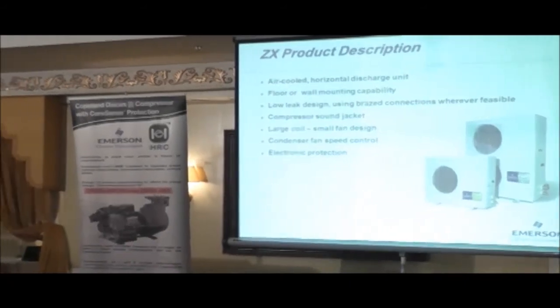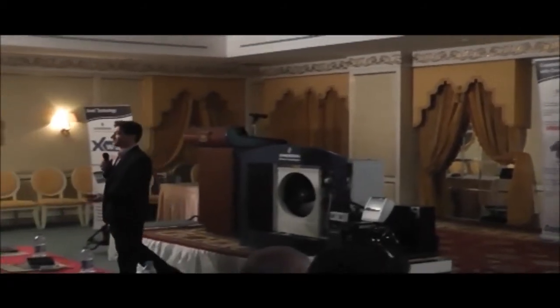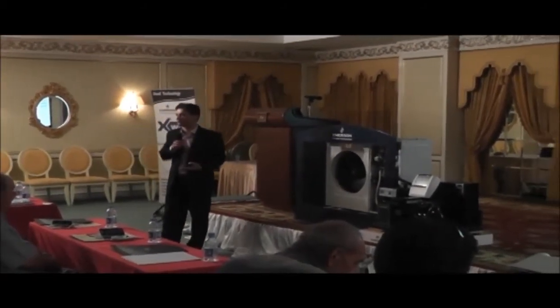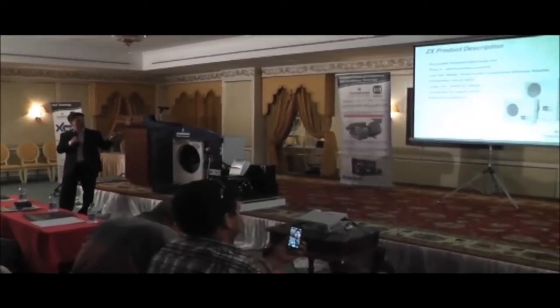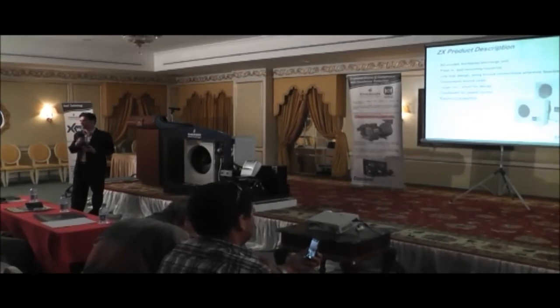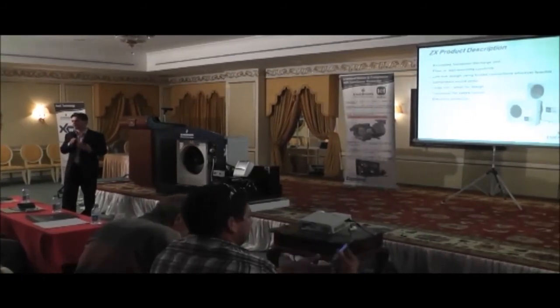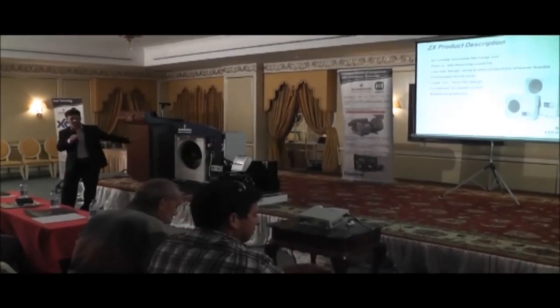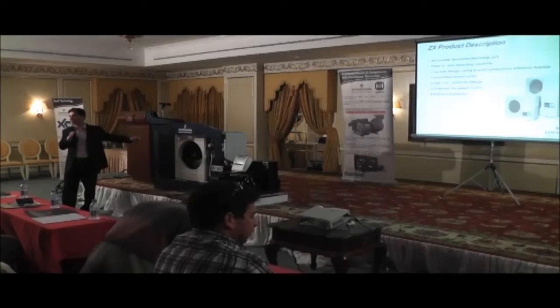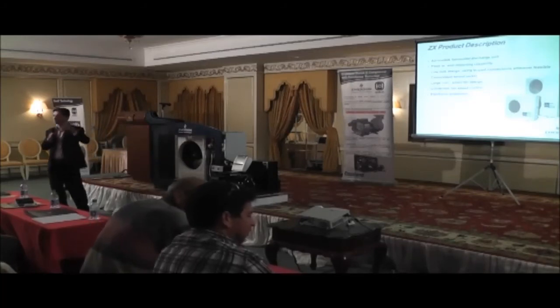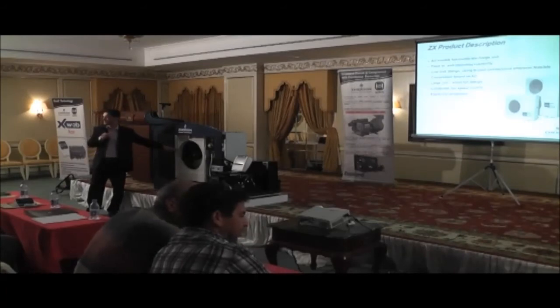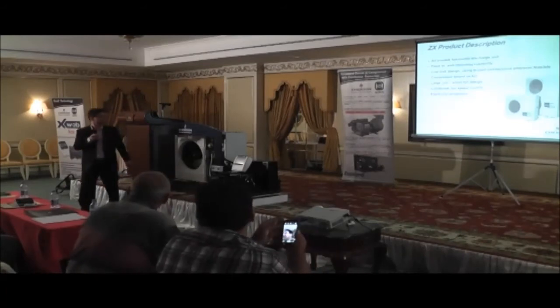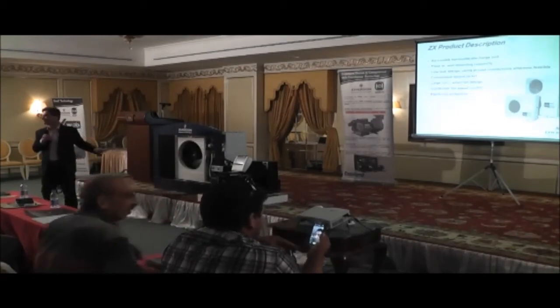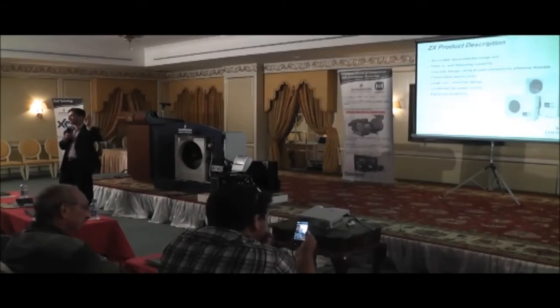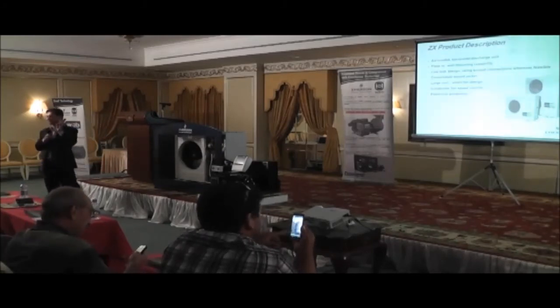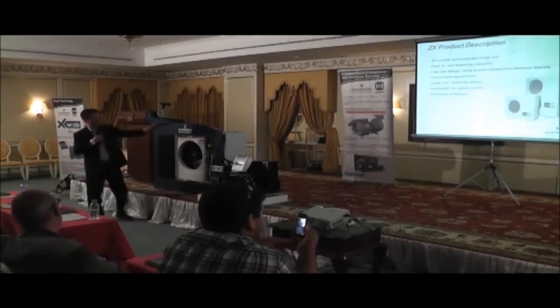We've got a scroll compressor in here. This compressor will have a sound jacket. The purpose of the sound jacket is to reduce the noise. We've got a large coil, small fan design. To try and design a condenser combination that can work in high ambient, one of the things we took into account in designing this unit was to reduce the noise level. So we've gone with a big coil, small fan. This is a 6-pole motor running at 900 RPM. It's got integrated condenser fan speed control, so as your ambient drops and it gets cooler at night, the fans will slow down, reducing the noise. And then we have the electronic protection.